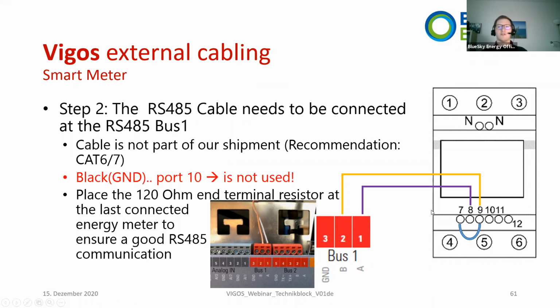And what is also very important, the last device of an RS485 connection needs to have an end terminal. This end terminal is applied by adding a wire. Really it's only a short wire from pin 7 to pin 9. Or please just follow the instruction which you receive with the system.